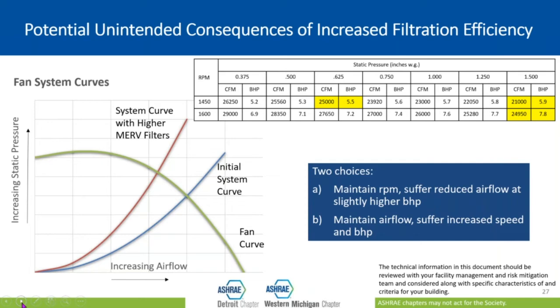So obviously these are the filters that remove 99.9% of particles, but we don't recommend them for a couple of reasons. One, many viruses are actually smaller than the size for which the HEPA filters are rated, but also the MERV rating system correlates to the minimum efficiency across the particle size for the filters, and how the filters operate. They actually perform their worst typically around 0.3 micrometers, both above and below this size range. The filters tend to be a little bit more efficient.